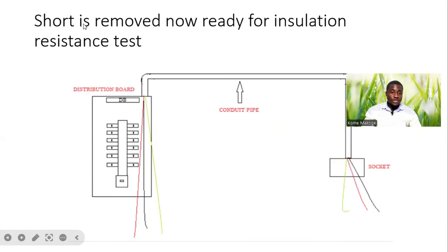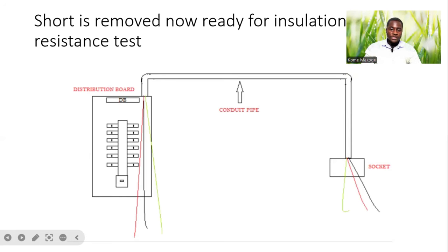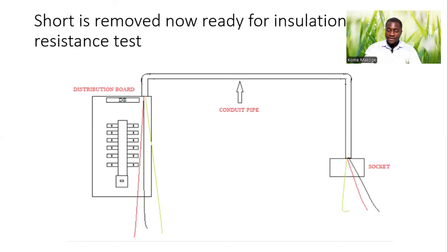Now the short is removed and we are ready for insulation resistance test. This is what we have to do — we remove the short which we had before from the DB side. As you can see on the field side, we have nothing shorted. We are now ready to perform our insulation resistance test.